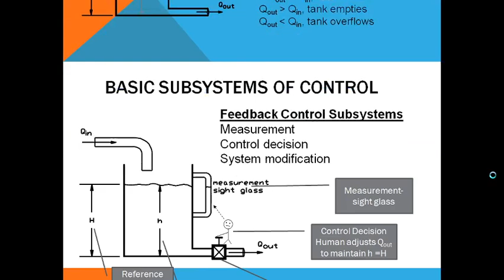Now the basic subsystem of a control is given in a feedback control subsystem where measurement, control decision and system modification take place. The same diagram is used again. Q in is the input, height is the reference set point where small h equals the control variable, and the process maintains tank level. The final control element, the valve, is there, and see here in the diagram a man is operating the valve. In the control decision, the human adjusts Q out to maintain h equal to the set point, and there is a measurement sight glass present.